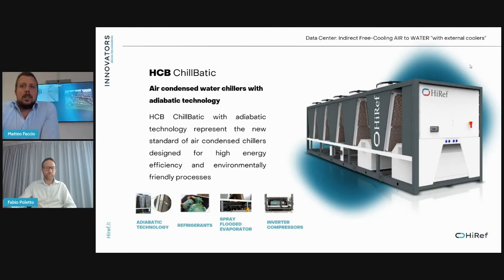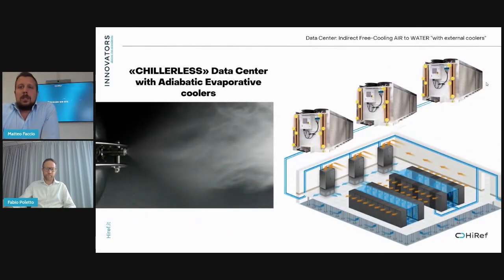Compressors are still mandatory, because we need to consider some worst-case scenarios, for example that we do not have water, or the external temperature is so high that the compressor must run in order to provide the cooling capacity. We need to say also that in some cases, in a specific region of the world, it's also possible to run a data center without chillers. So this is an example of a data center with only adiabatic coolers outside, but even in this case, the customer always likes to have some mechanical cooling as a real emergency condition.